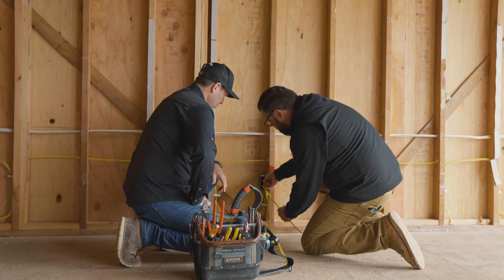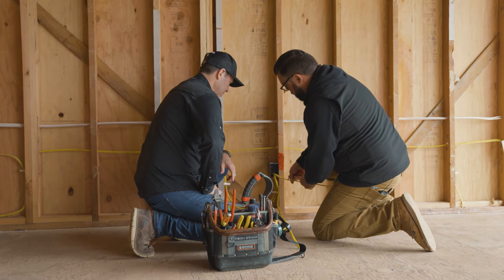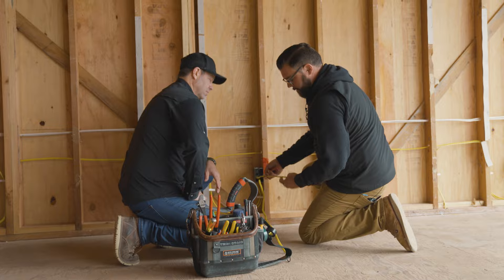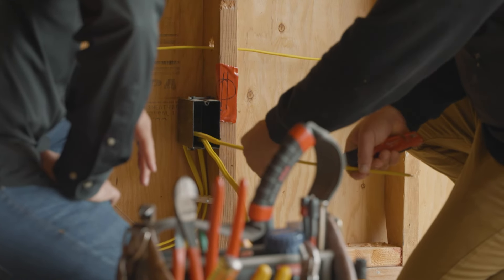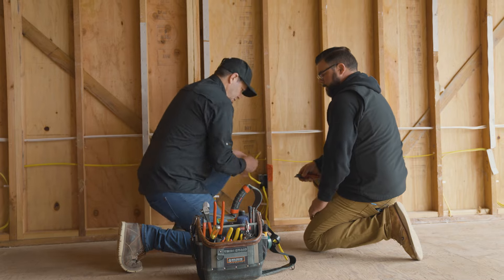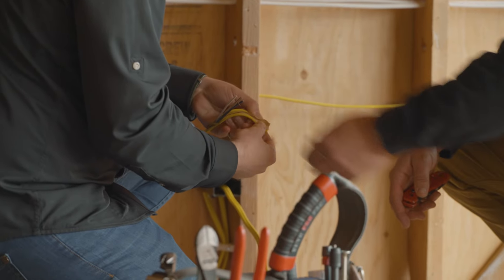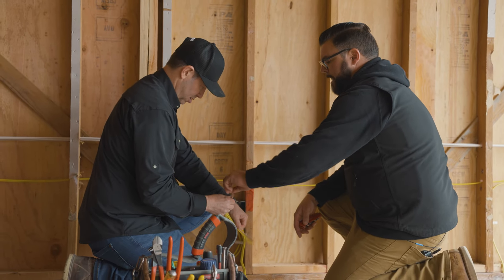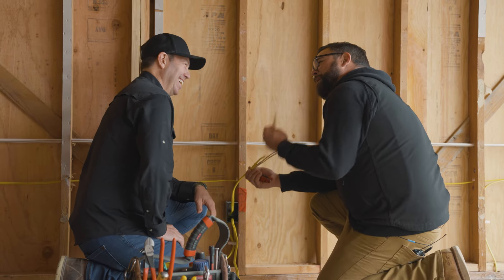We're right in the back of the box and I'm going to show you on a long one. You're right in the middle — this is where an apprentice will get cut quick. But once you're started, you're not worried about that middle conductor because there's a bare ground wire, and you can actually guide right along that. That's why we're cutting down the center. Peel that apart and see how easy that is. This is a 12-2, but it's kind of deceiving — they don't count the ground as a wire. There's paper in there, which acts as an insulator.